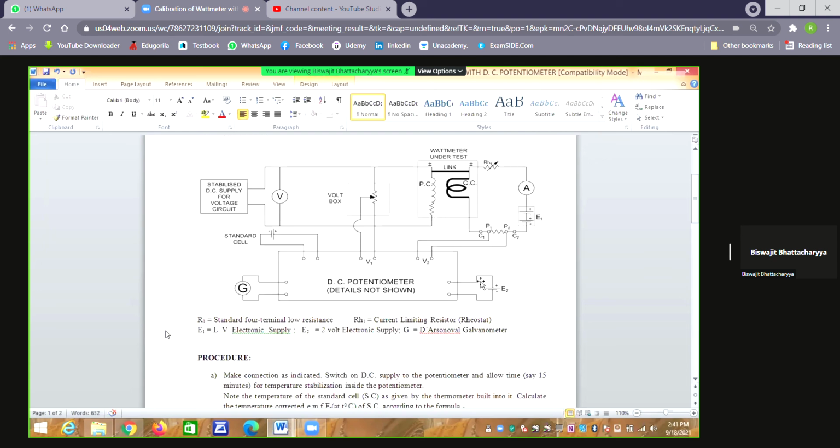In the voltage measuring circuit, the voltage drop in the contact should not come. Therefore, the contact drop should take place outside the region of the potential terminal. Therefore, potential terminals are placed inside, and contact drops happen outside the zone of the potential terminals and are not measured by the voltage measuring circuit.